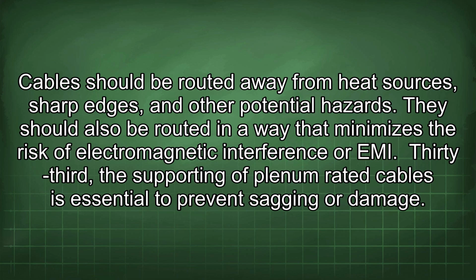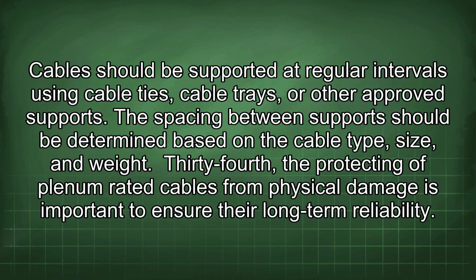33rd, the supporting of Plenum-rated cables is essential to prevent sagging or damage. Cables should be supported at regular intervals using cable ties, cable trays, or other approved supports. The spacing between supports should be determined based on the cable type, size, and weight.